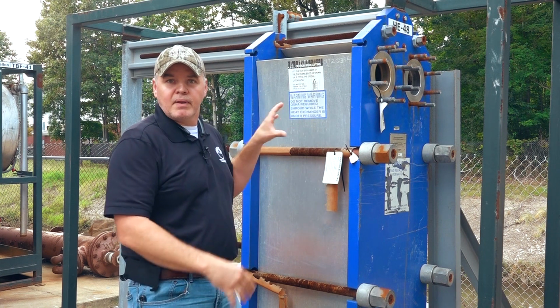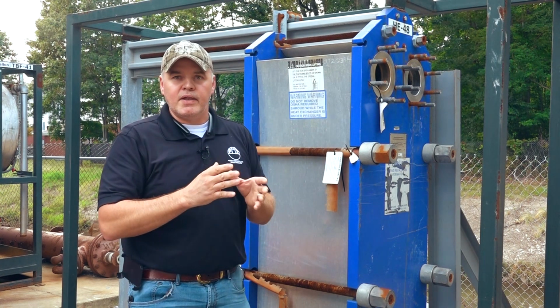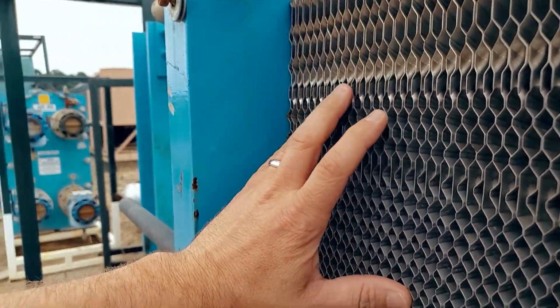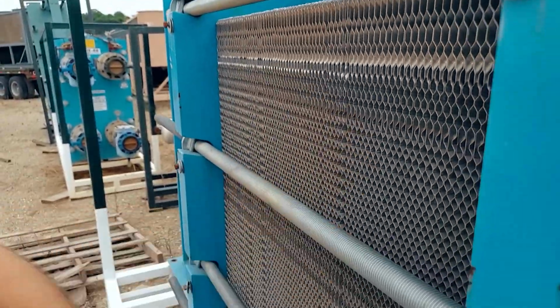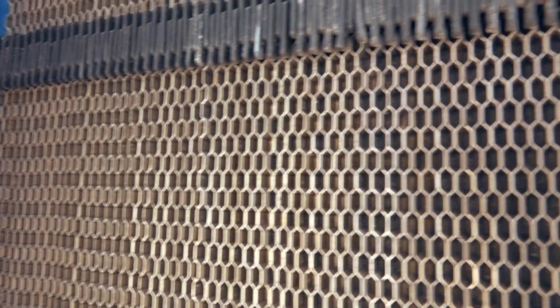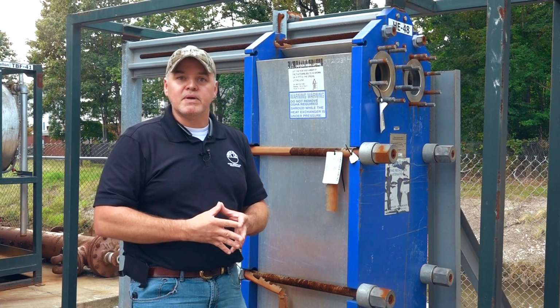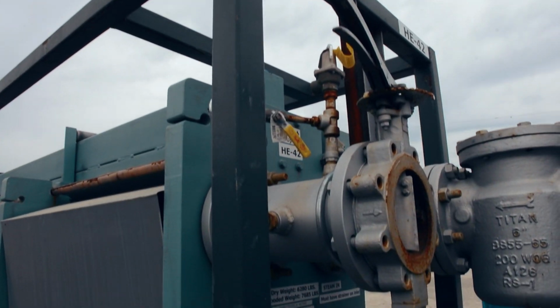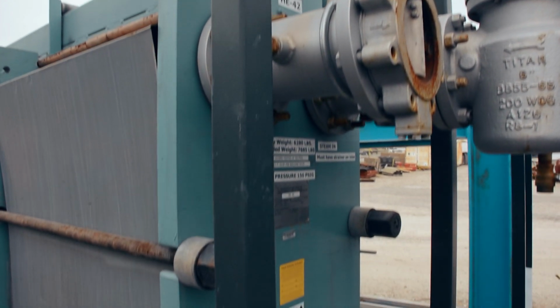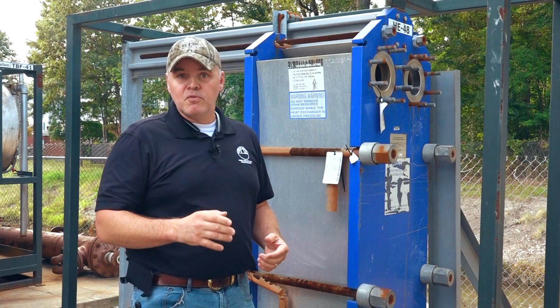So there are corrugated plates that are fitted to one another, and they're bound with a gasket that creates a seal as well as a channel between each one. Each plate is stacked, alternating between hot and cold side. The hot, for example, would be steam or hot water, and then the cold represents a process medium. So these plates will be bound together by a fixed or stationary cover and a movable cover.